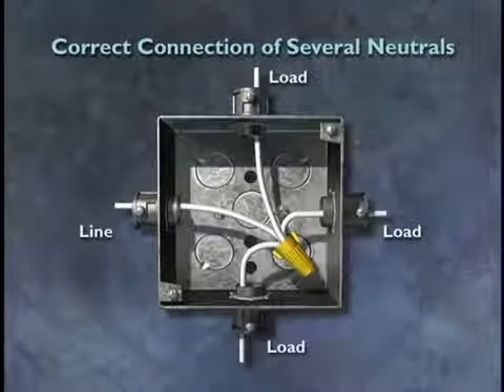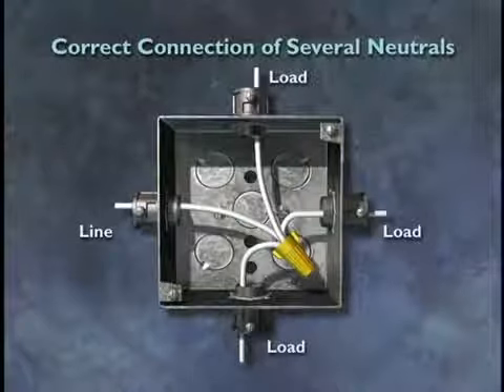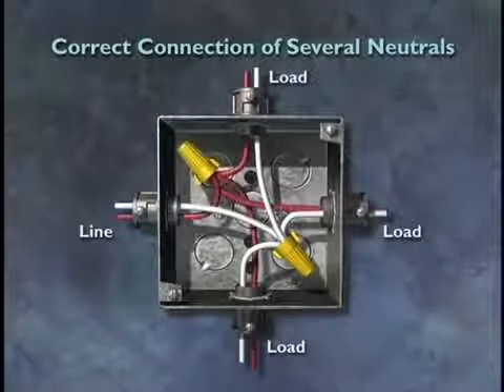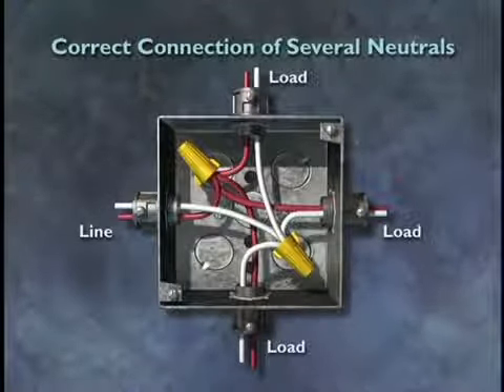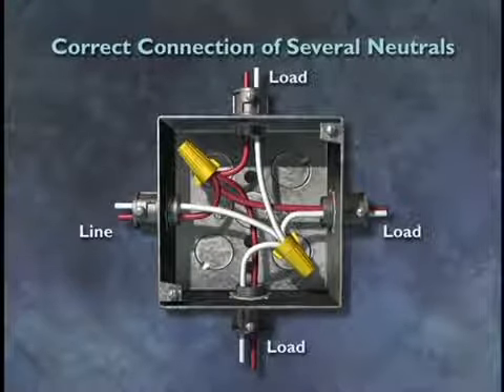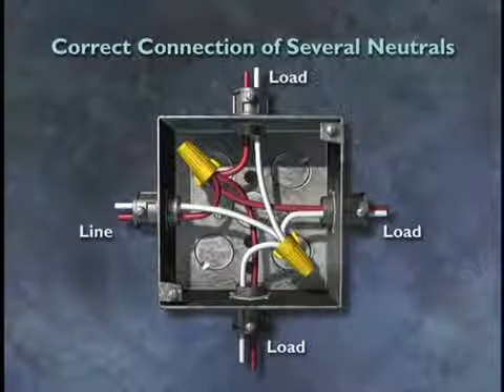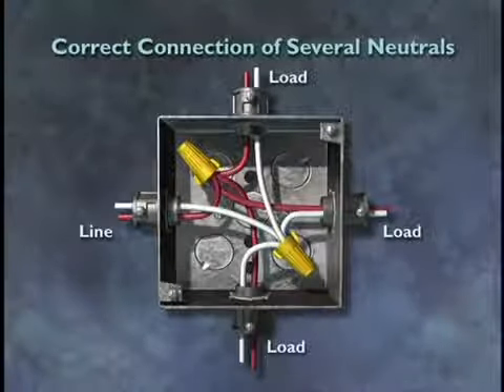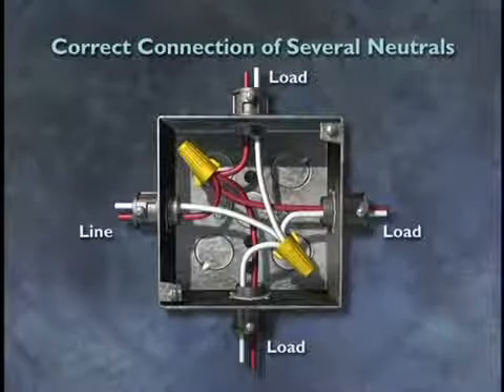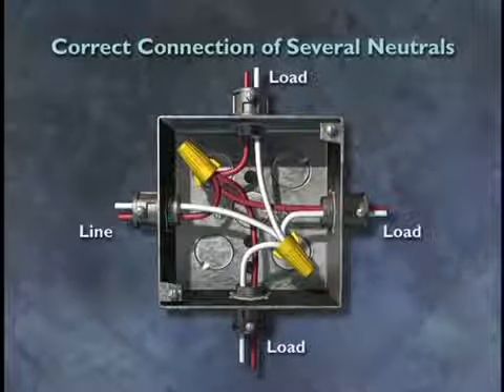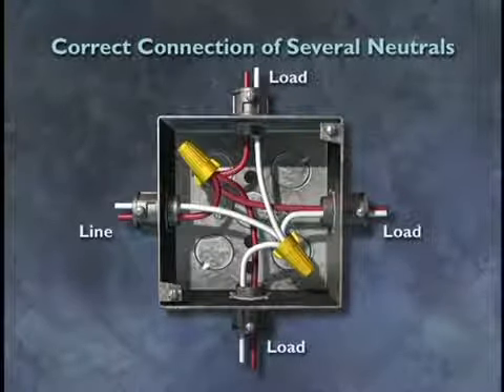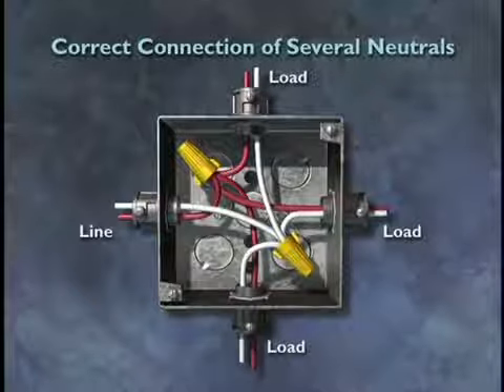Now, there's nothing wrong with using one wire nut to connect all neutrals in a junction box when there's only one branch circuit present. It is only when a junction box is shared by two branch circuit feeds that you must keep the neutrals from each circuit separate. In this junction box, the neutrals from three loads are connected to the returning neutral. There is no splitting of the return current and no net current.